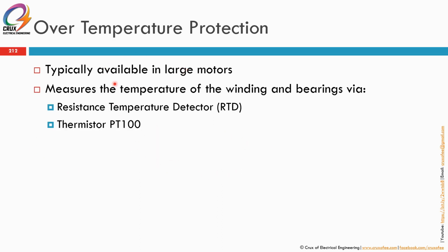Okay, over temperature protection. Typically, it's used in the large motors. For LV motors, we rarely use this over temperature protection. So it can measure the temperature of the winding and the bearing using resistance temperature detector, RTD, or using the thermistors, PT100, embedded within the winding or at the bearing lah, drive end and the non-drive end lah, DE and NDE.